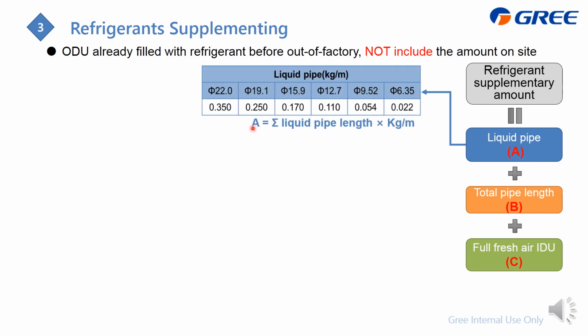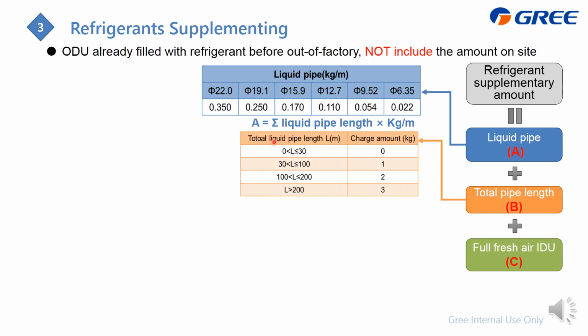First, for the A part, you can find it from this calculator. This is the total liquid piping length for different sizes, and then you type it in according to this table, so you get the A part. For the B part, it is the total piping length, which is the total liquid piping length. If, for example, the total length is 65 meters, it goes to this, so you need to add an additional 1 kilogram.